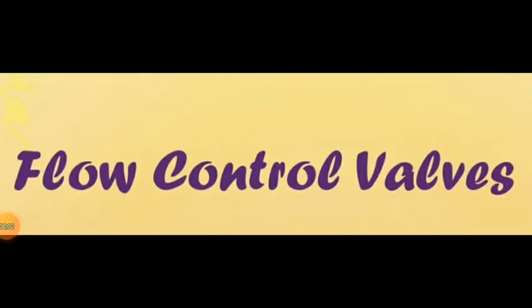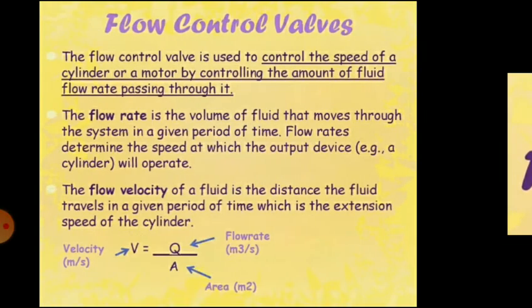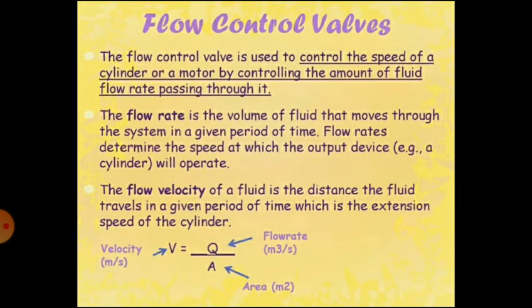Good morning. Today we will discuss regarding flow control valves used in hydraulic systems. The flow control valve is used to control the speed of a cylinder or a motor by controlling the amount of fluid flow rate passing through it. Flow control valves are used to regulate the flow of fluid in a hydraulic system. The flow rate is the volume of fluid that moves through the system in a given period of time, and flow rates determine the speed at which the output device, for example a cylinder, will operate.